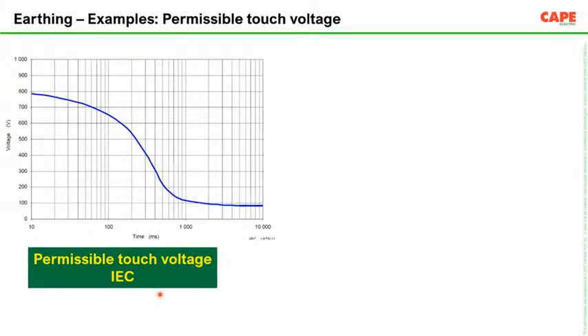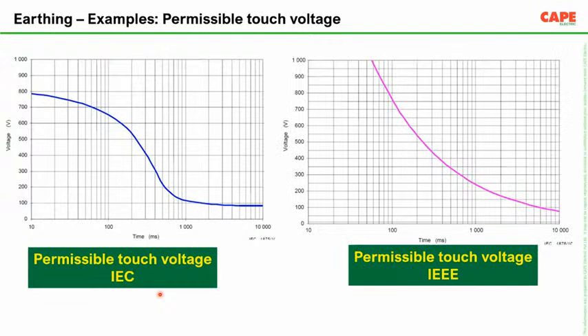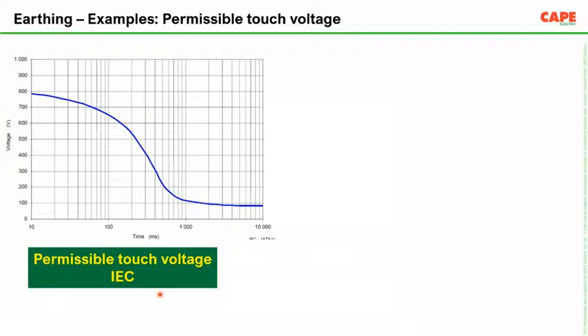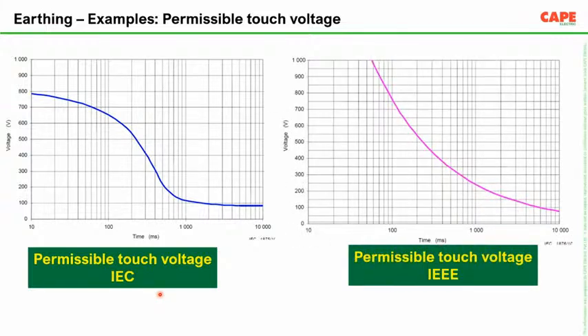Always, the safety with respect to earthing, the purpose of earthing, is to ensure that the touch voltages are limited within the permissible limit. IEC gives a permissible limit. You can see here on the x-axis the time, and on the y-axis the voltage. Say for example, in 100 milliseconds the voltage has to be limited to less than 700 volt, maybe 650 volt, and in 1 second it has to be something about 100 volt, a little bit more than 100 volt, and in 10 seconds it has to be less than 65 volt.